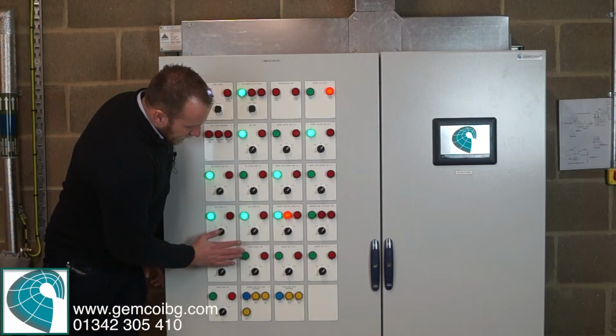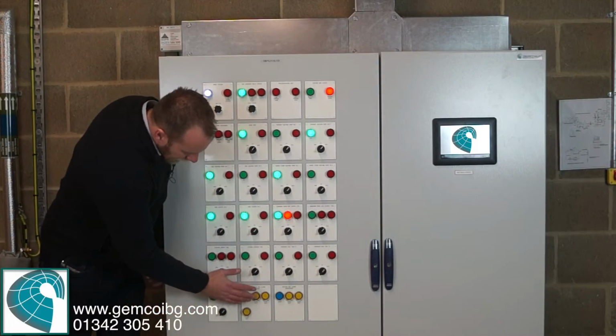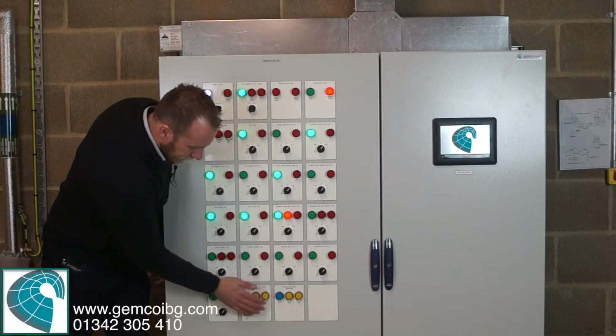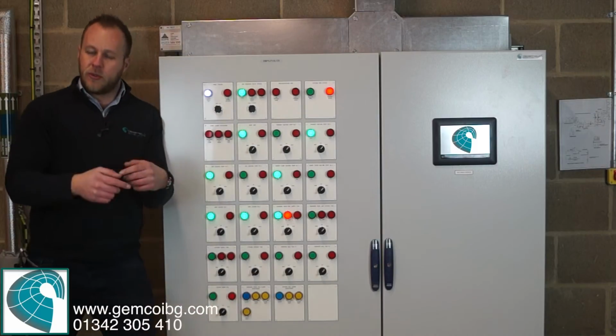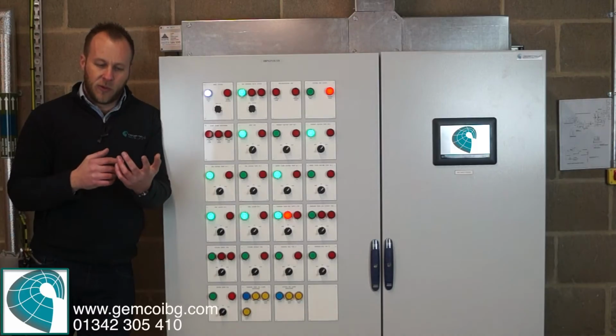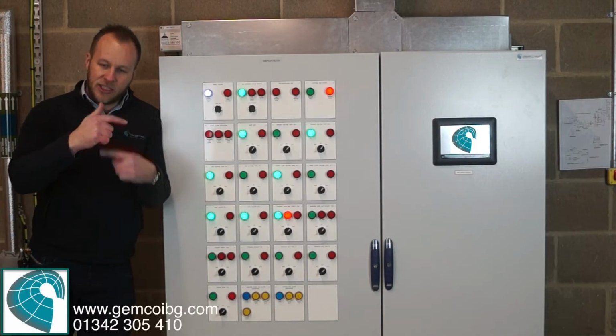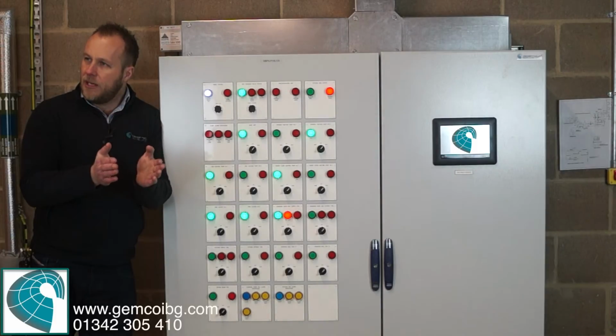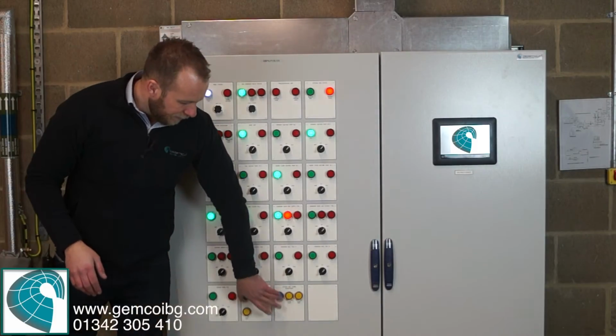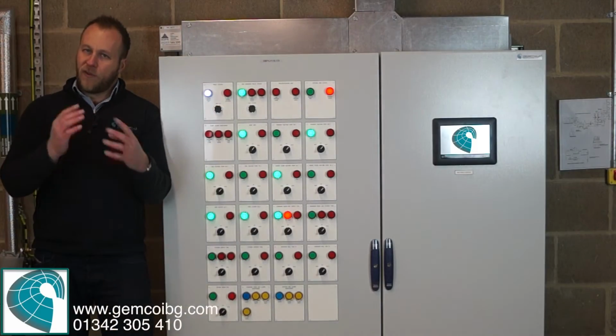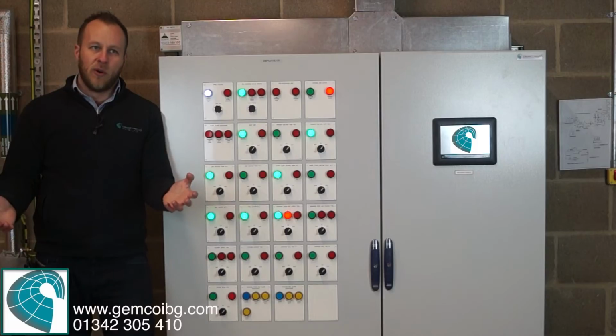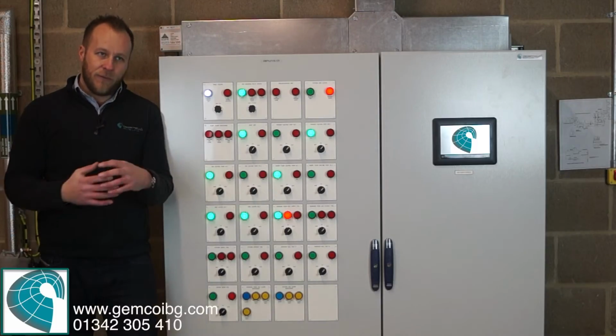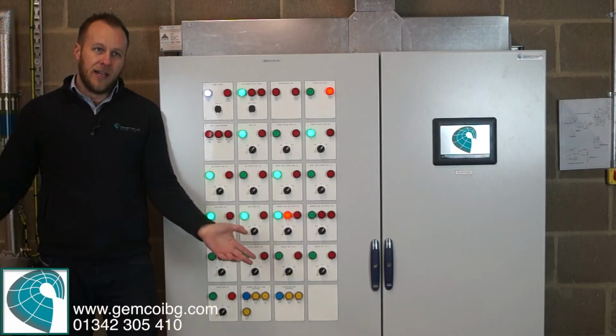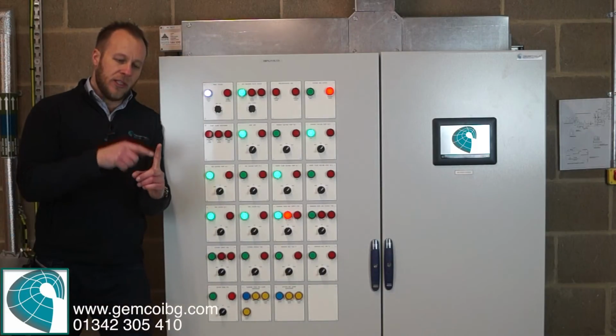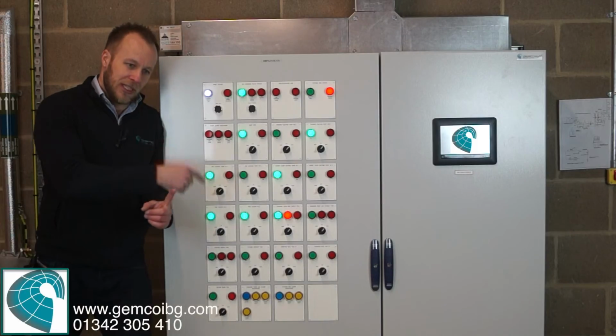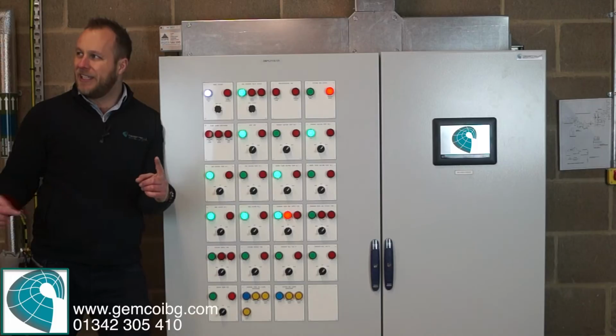So that's how your temperature control works on your air handling units. And then we've got some monitoring down here of filters and frost. On each fan you've got a frost coil. It's a heating coil, but it's not used to temper the air. What it's used for is to protect the heating coil. So it just modulates to maintain 10 all the time. If it goes below 10, we've got hardwired frost stats that say the valve must have failed because it's 5 degrees, shut the fan off. And what that's for is to stop freezing cold air freezing your coils, cracking your coils, and then a flood. All right, so you've got a frost coil that's just protection, and then you've got a frost stat that protects the frost coil, and the frost coil protects the heating coil.